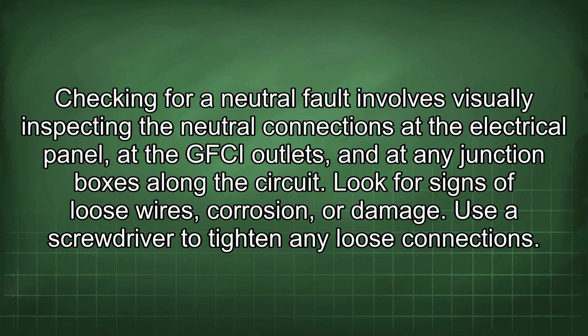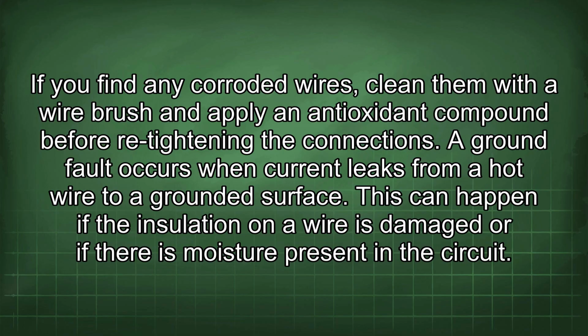Checking for a neutral fault involves visually inspecting the neutral connections at the electrical panel, at the GFCI outlets, and at any junction boxes along the circuit. Look for signs of loose wires, corrosion, or damage. Use a screwdriver to tighten any loose connections. If you find any corroded wires, clean them with a wire brush and apply an antioxidant compound before retightening the connections.